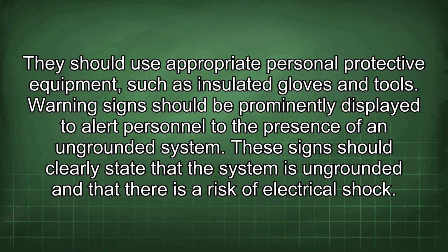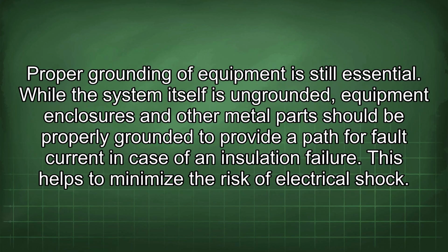Warning signs should be prominently displayed to alert personnel to the presence of an ungrounded system. These signs should clearly state that the system is ungrounded and that there is a risk of electrical shock. Proper grounding of equipment is still essential. While the system itself is ungrounded, equipment enclosures and other metal parts should be properly grounded to provide a path for fault current in case of an insulation failure. This helps to minimize the risk of electrical shock.